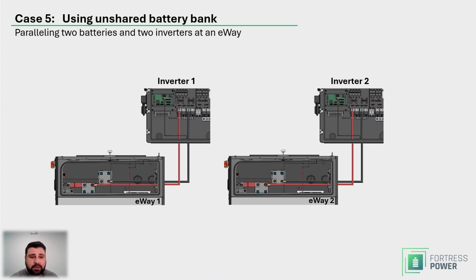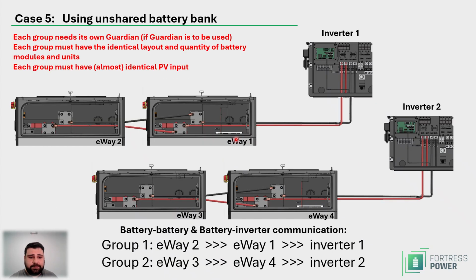Matter of fact, we can take a look here as well. So you have a group of 2 eWays, and here the same, you have eWay 3 and eWay 4. What happens is that this group connects to inverter 1. So inverter 1 has its own small battery bank of 2 eForces, or stacks of eForces, one with its own eWay on the top, and you have inverter 2, again 2 stacks of eForces, each with its own eWay, eWay 3 and eWay 4. What is extremely important here is that each group, if guardians are used, each group receives its own guardian, right? Because there is no communication between these groups as such.